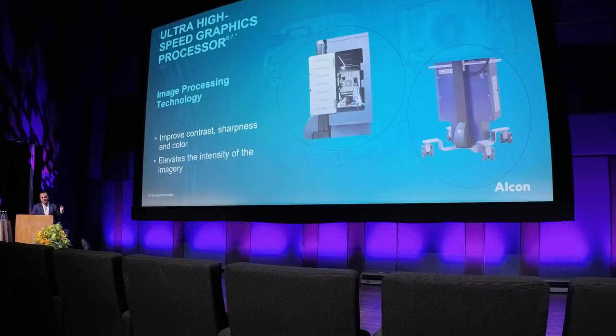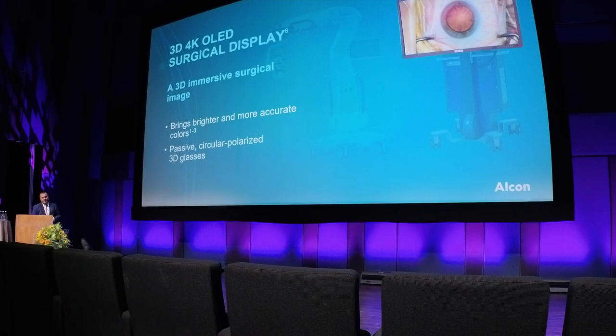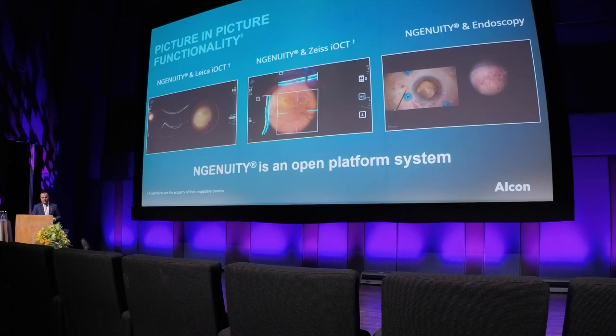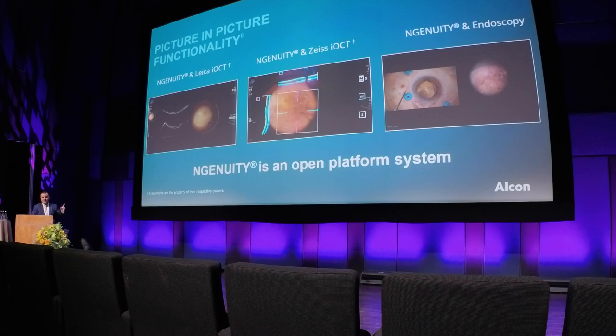The camera is connected to a high-performance PC which is responsible for seamless, fast image creation with as little latency as possible. The OLED display is really important — it's medical grade and passive, which will not create any fatigue on the surgeon. It's also an open platform. You have picture-in-picture capabilities and you can connect whatever source of information you want, shown beside the main screen during surgery.